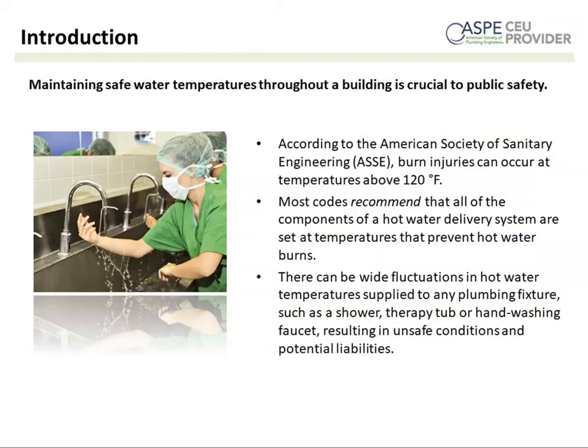As I think probably most are aware, temperatures and burns become excessive at around 120 degrees. That's when burns can actually take place. So most codes recommend that for all the components in a hot water delivery system, the temperatures are set to prevent excessive hot water. And typically at the point of use, that revolves around setting limit stops and making limit stop adjustments.